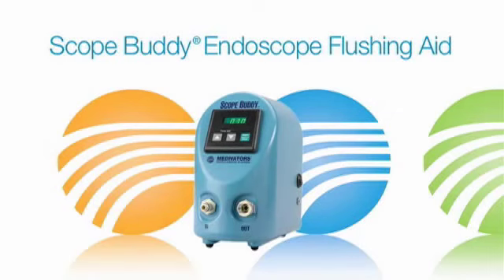Scope Buddy is designed to provide maintenance-free operation and long-term use. Following the daily routine of performing the flow validation quality test and the decontamination procedure will verify system functionality to manufacturer's recommendations and specifications. Scope Buddy contains no user-serviceable internal parts or components. Routine inspection of all tubing sets is required. Never use tubing which is questionable or suspect. Only use tubing sets which have been visually inspected and verified to be good. Do not use alcohol-based products in or on Scope Buddy. Alcohol is not compatible and should never be used to clean, flush, or rinse Scope Buddy.